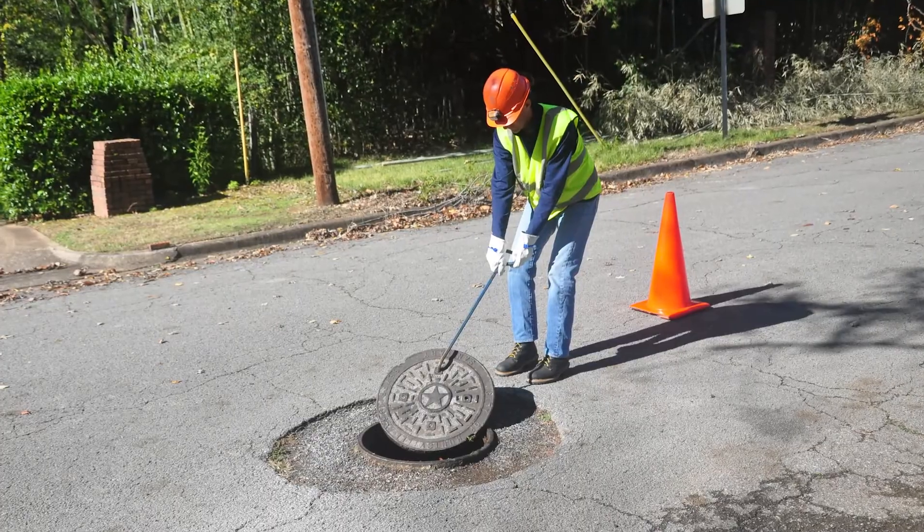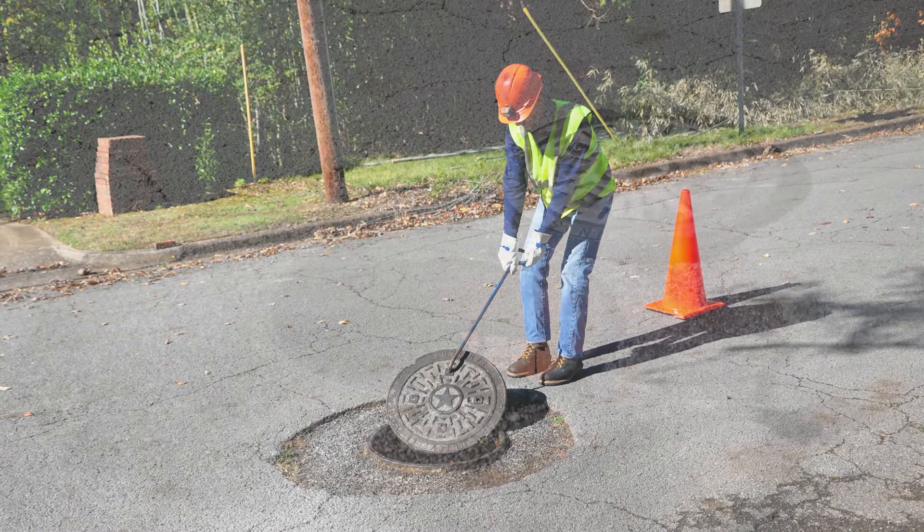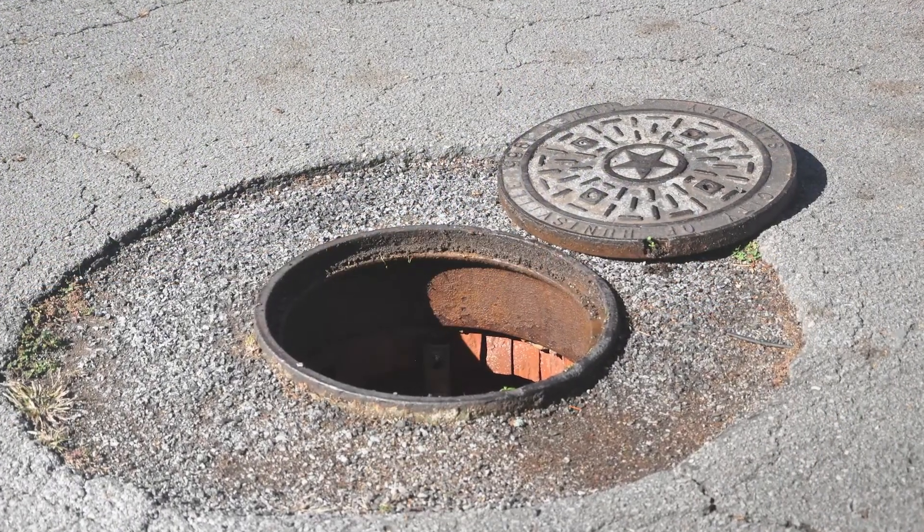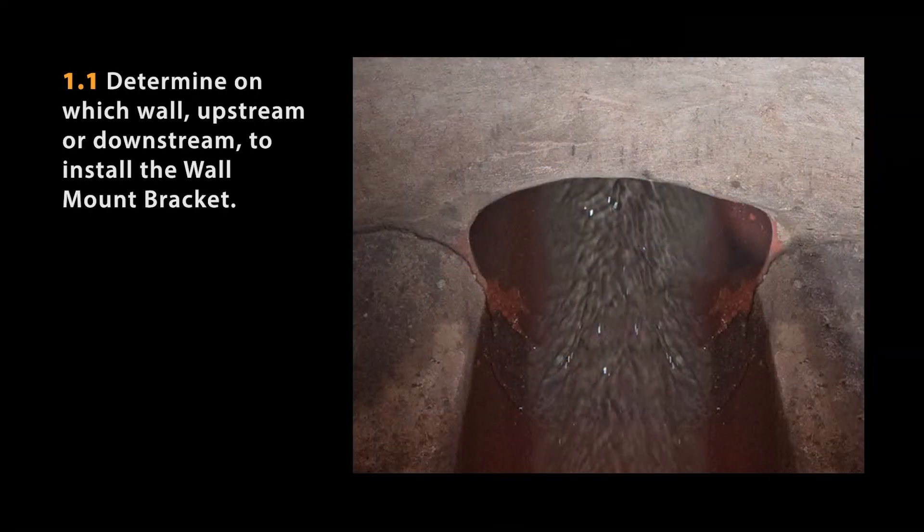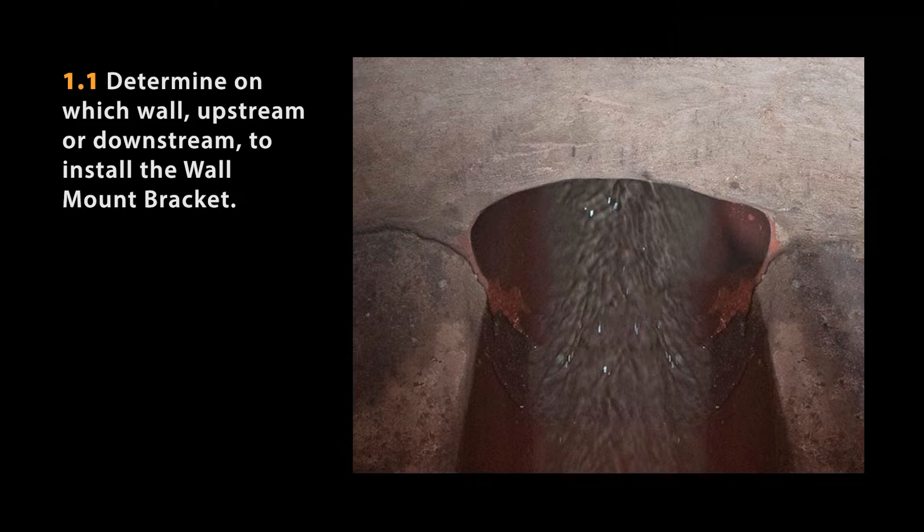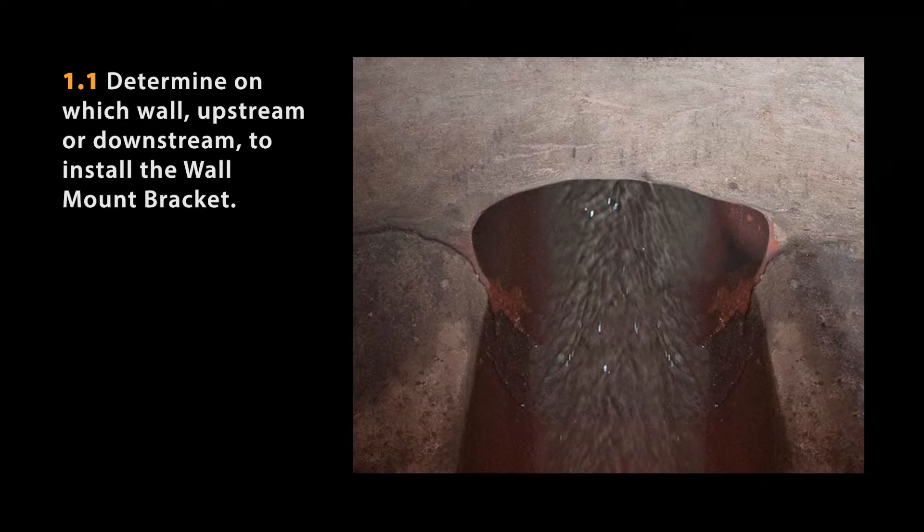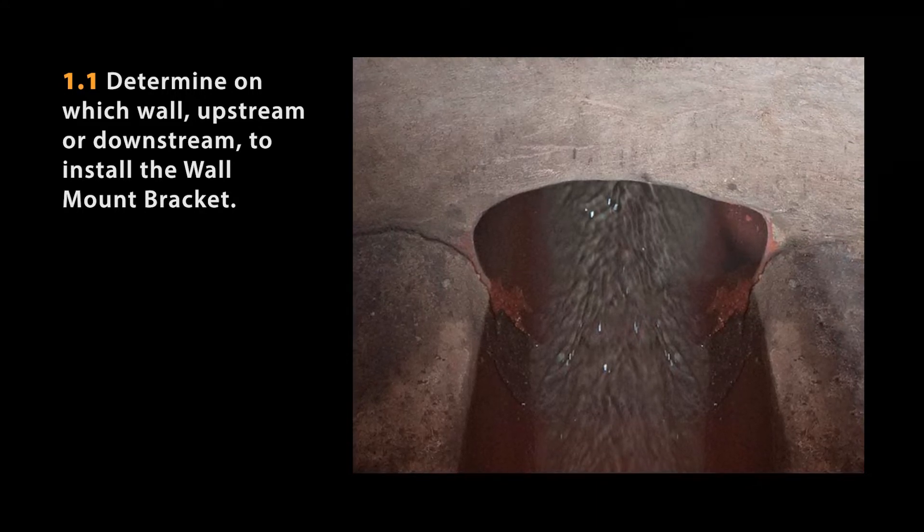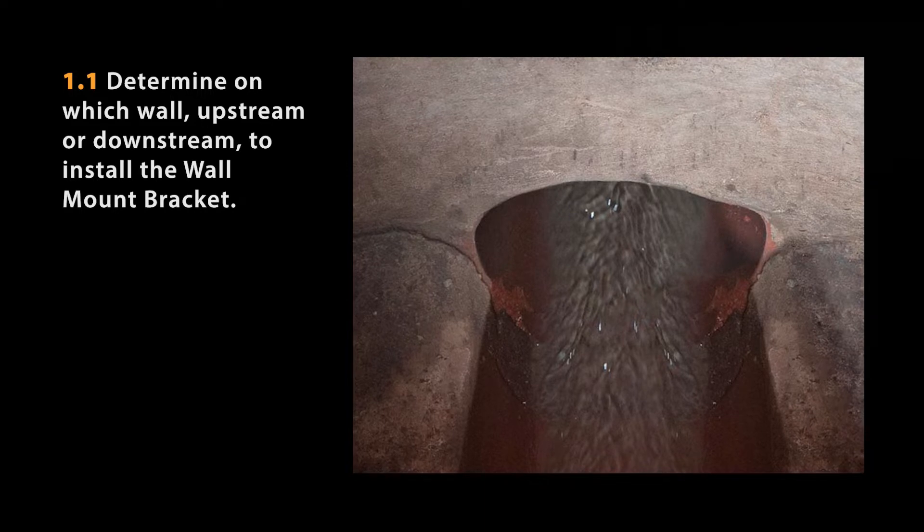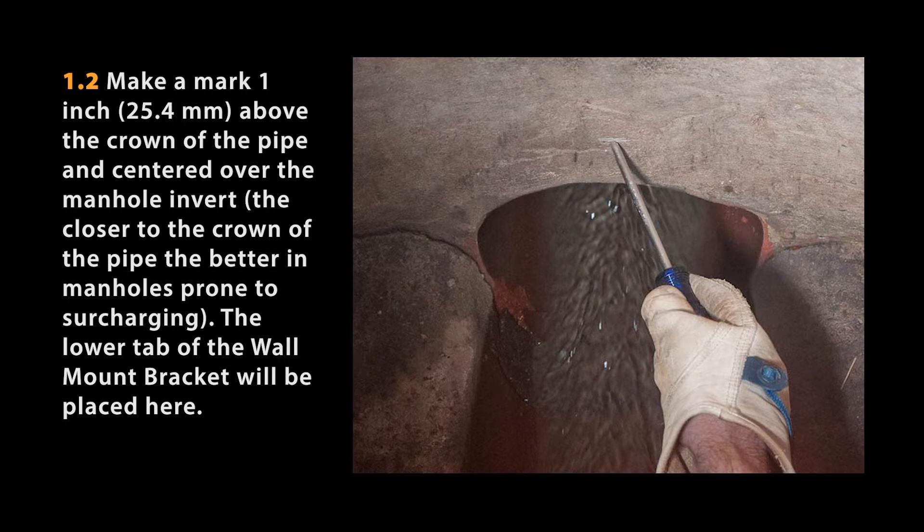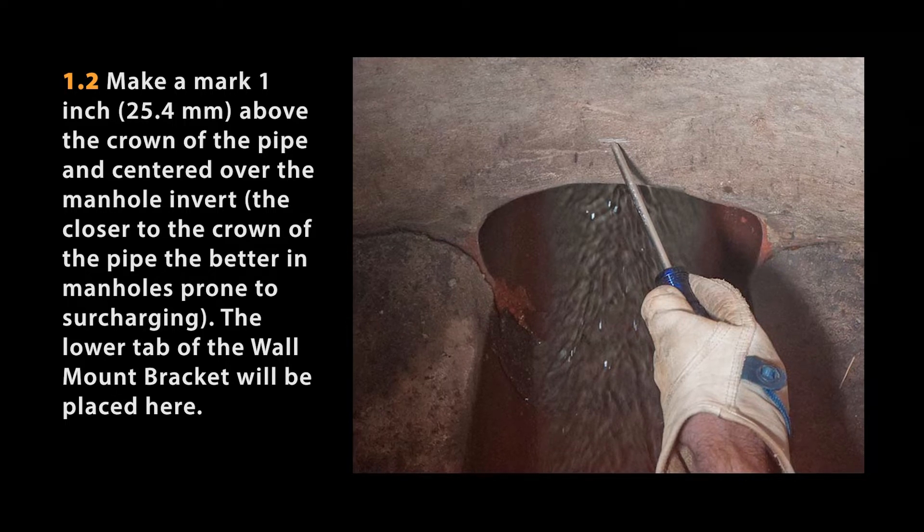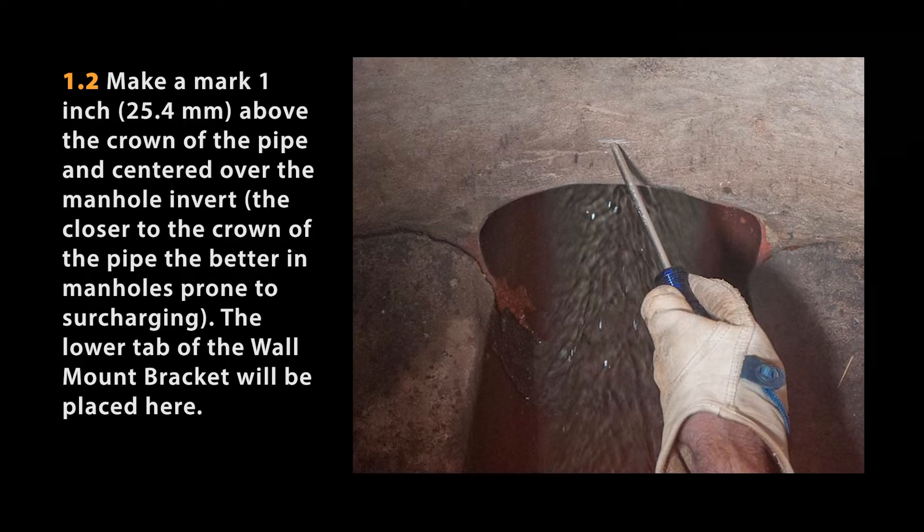Once on site and ensuring that you are following all required safety procedures, descend the manhole to install the wall mount bracket. Determine whether to install the wall mount bracket on the upstream or downstream wall. In manholes prone to surcharging, ADS recommends installing the bracket on the downstream side of the manhole. Make a mark 1 inch or 25 millimeters above the crown of the pipe and centered over the invert.